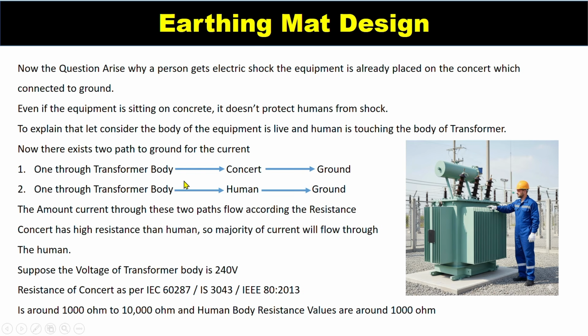One is through the transformer body, concrete and ground, and another is through the transformer body, human and the ground. The amount of current through these two paths flows according to the resistance. Concrete has a higher resistance than a human, so the majority of current will flow through the human. Suppose the voltage of the transformer body is 240 volts. The resistance of the concrete as per IEC 60287 and IEEE 80 is around 1000 ohm to 10,000 ohm, and the human body resistance is around 1000 ohm.